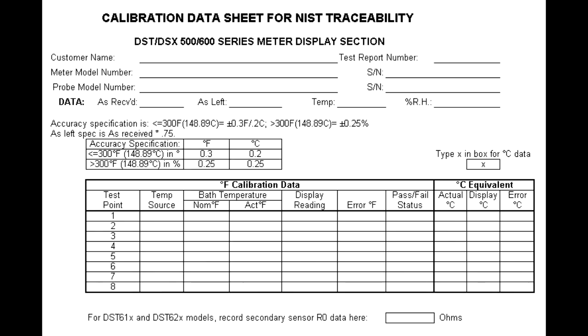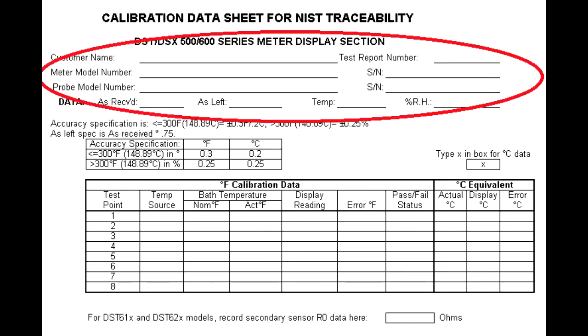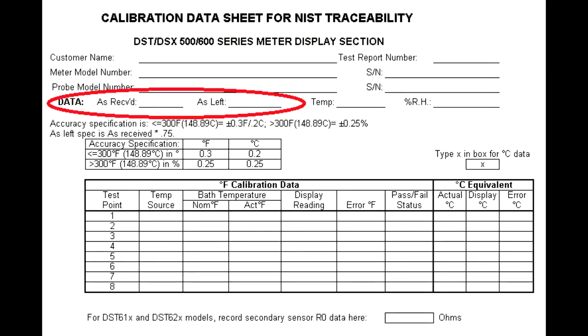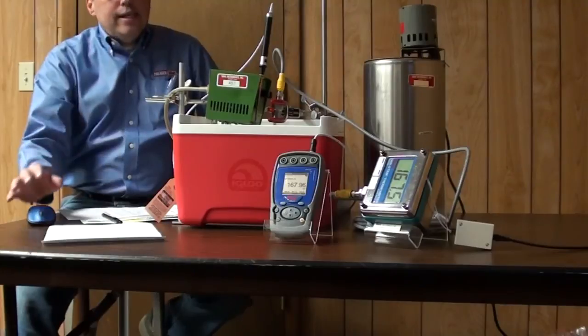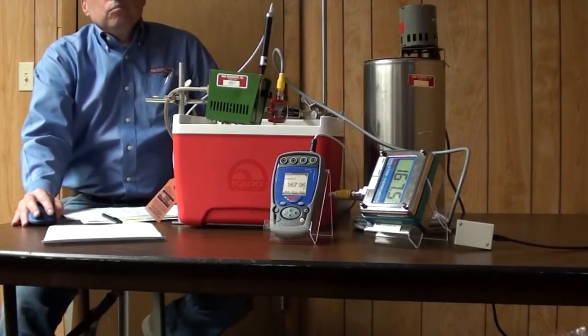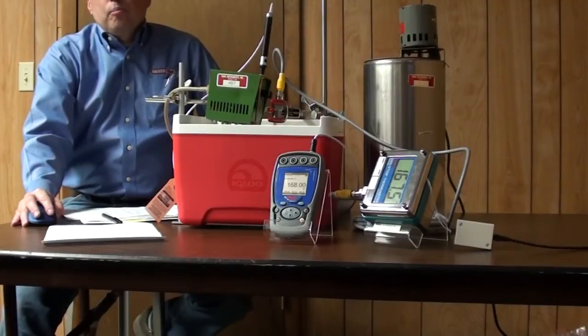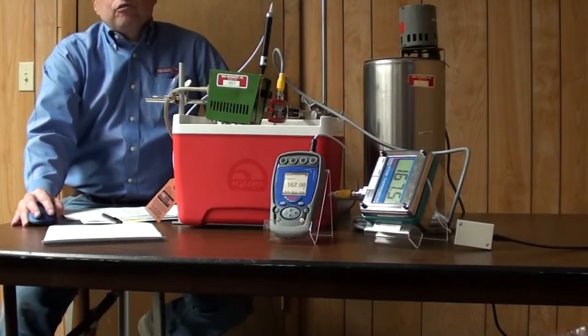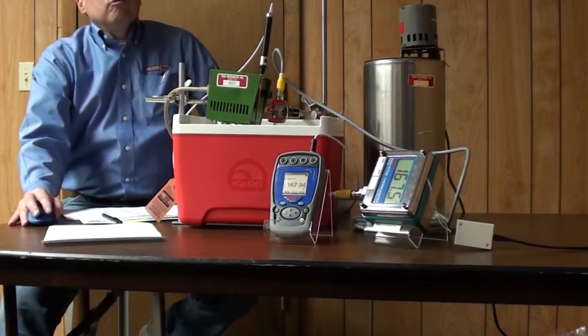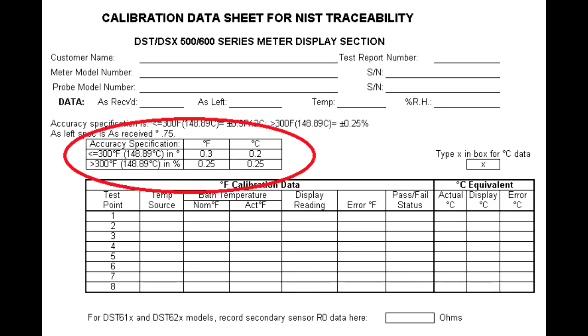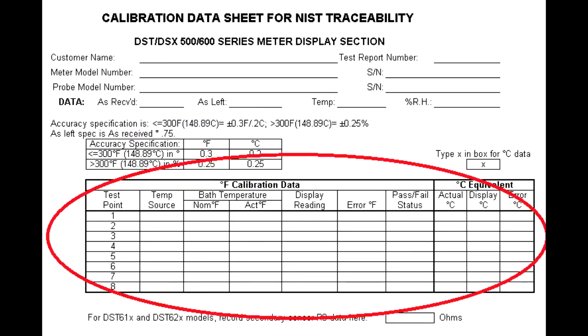The second sheet of that is where actually the data goes. And this particular one was laid out for a single calibration. So again, we have information on our unit up here that's being calibrated. We have data type here, as received and as left. So when we're calibrating, and we'll get into this in more detail, basically, if we've not done any adjustment, some of these used to be called before adjustment and after adjustment, and it's important you know that information. We have our specifications here, and our data gets filled out in this field here.